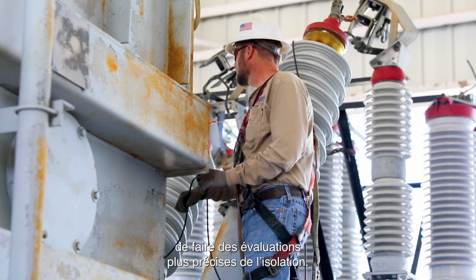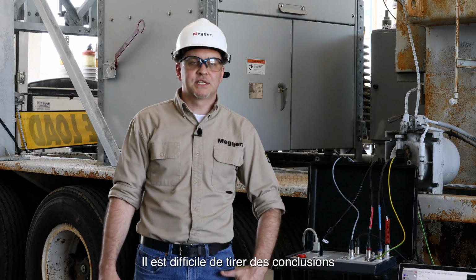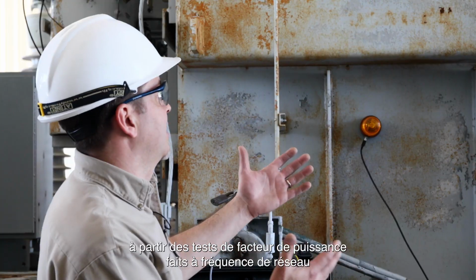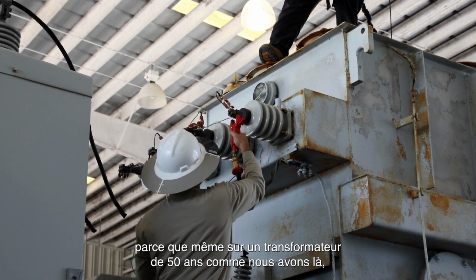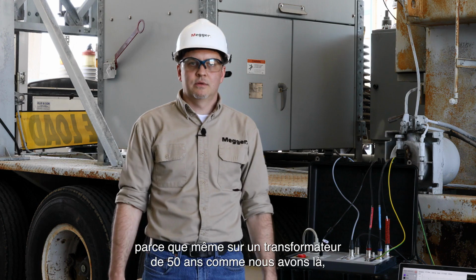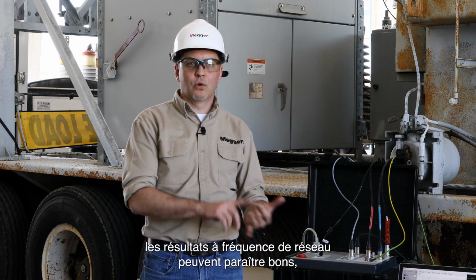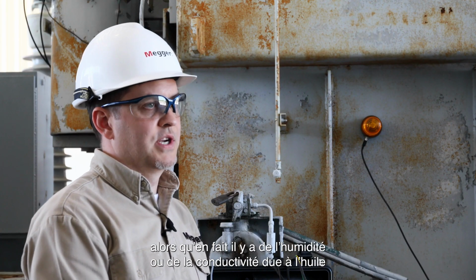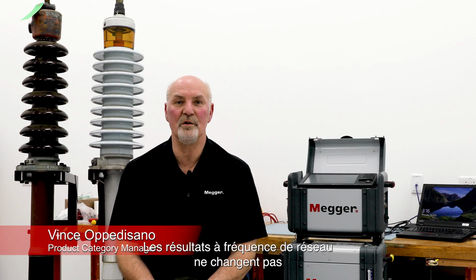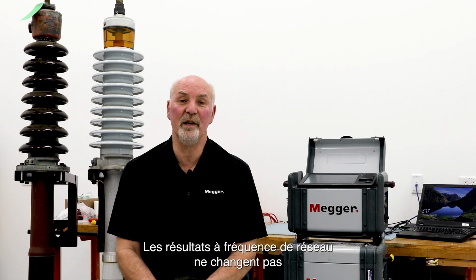It's difficult to draw conclusions from line frequency power factor testing because even on a 50-year-old transformer like we have here, results at line frequency may appear good when in fact there's moisture or oil conductivity happening within the transformer. The results at line frequency do not change until the problem is quite severe.